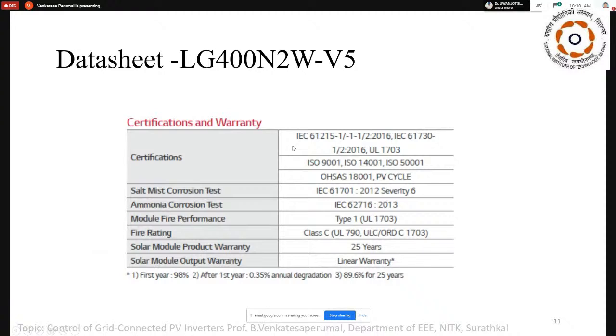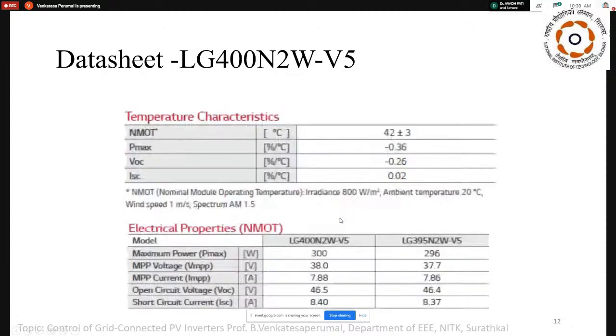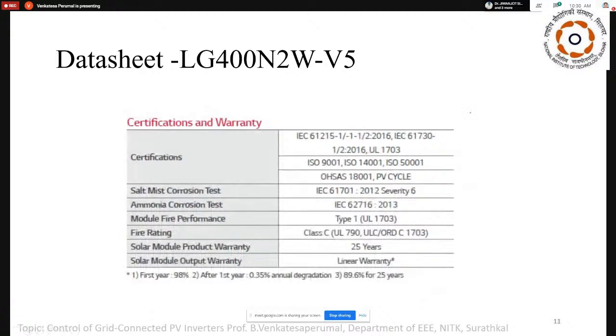Before going to those, other parameters in the panel are the standards it has to meet. If you look at the UL conditions, one more parameter comes into the picture, which is string voltage. If I have one panel with 72 cells and a voltage of 40 volt, I cannot connect 100 panels in series. 100 panels into 40 volt would be 4000 volt. This is not permitted. The string voltage is normally restricted to 1000 volt.